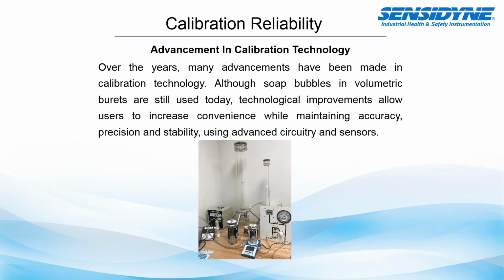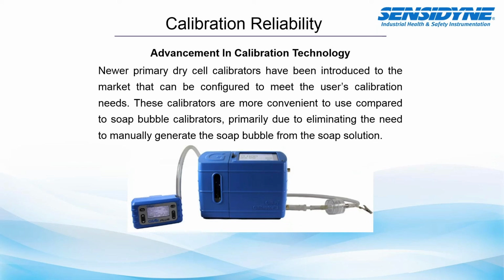Lastly, let's talk about some advancements in calibration technology. Now, over the years, many advancements have been made in calibration technology instruments. Although soap bubbles and volumetric burettes are still used today, some technological improvements allow users to increase convenience while maintaining accuracy, precision, and stability using these advanced circuitry and sensors that are placed in today's instrumentation. Newer primary dry cell calibrators have been introduced into the market that can be configured to meet the user's calibration needs. These calibrators are more convenient to use compared to the soap bubble calibrators of yesterday, primarily due to eliminating the need to manually generate the soap bubble from the soap solution.